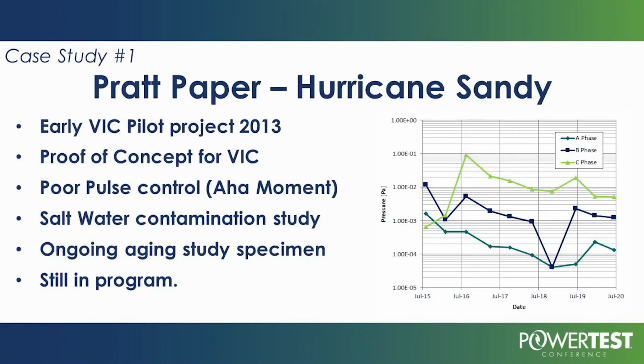We had an aha moment when we realized that by pulsing these interrupters, we could get more energy and more effects, so we've gone to a pulse model. We're also doing a saltwater contamination study on them, and we have an ongoing aging study going on these interrupters. These interrupters are still in the process. If you look to the right, you can see some of the process that we made in taking these interrupters from a certain pressure and reducing the pressure and holding it there over a 9-year period.